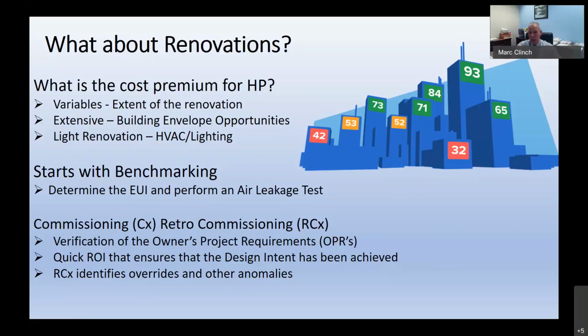I'm a believer of commissioning and retro commissioning. Commissioning is the verification to ensure the owner's project requirements are being incorporated. Just because there is a design that tells a mechanical contractor and a controls contractor what to do doesn't necessarily mean that it will happen. It requires a third party to come in and do that commissioning to trust but verify that these OPR requirements are being achieved. It's a quick return on investment to ensure that the design intent is being achieved.